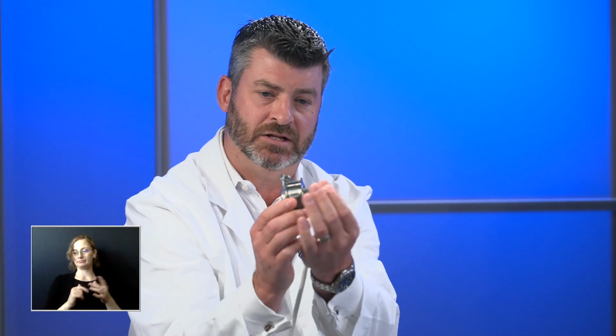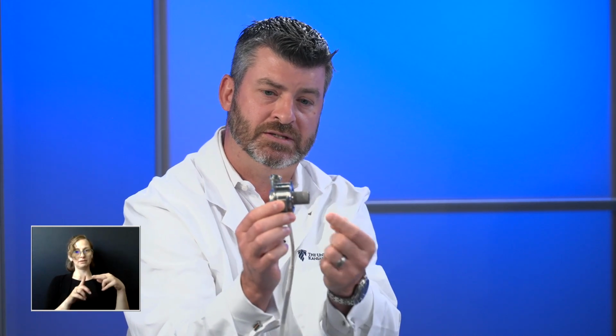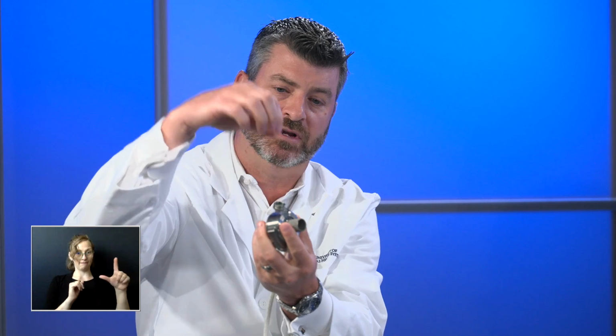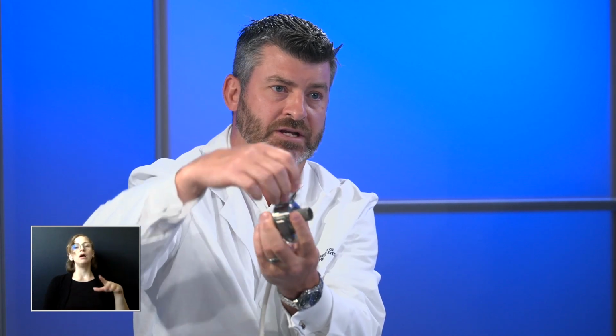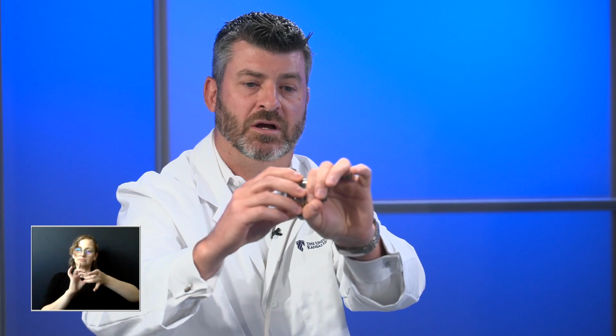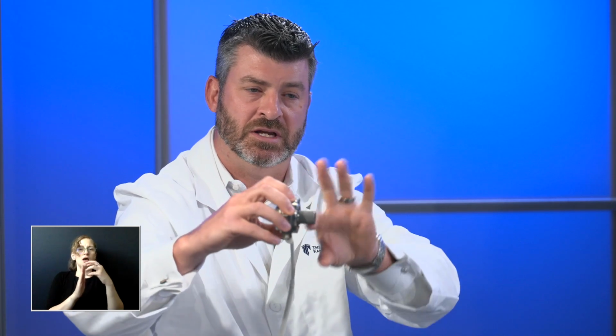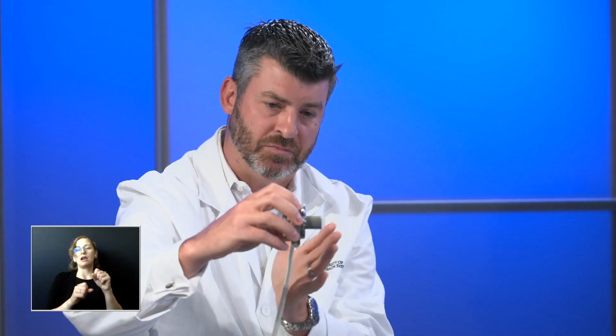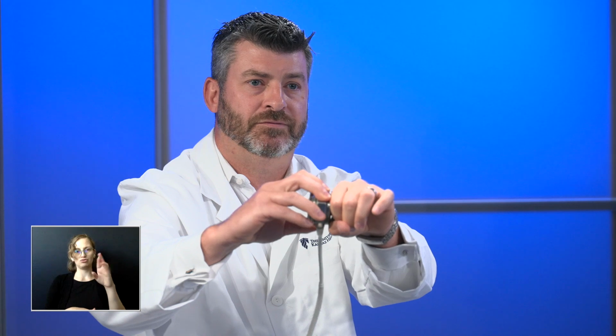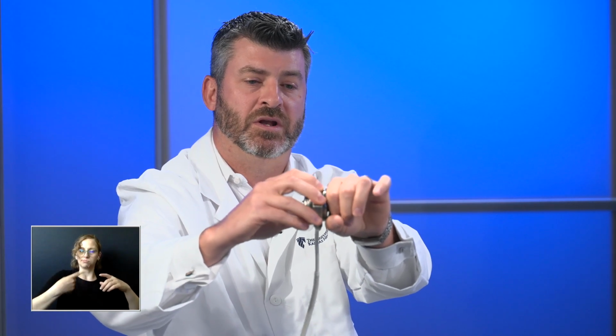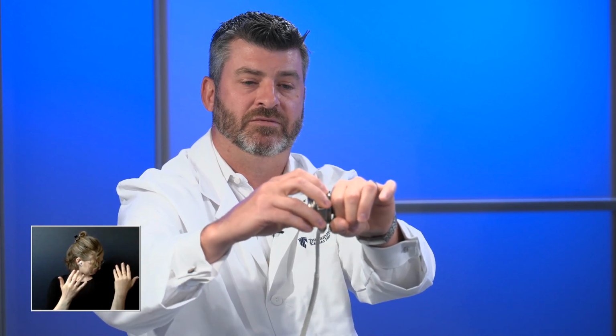this pump sticks into the left ventricle, and what this problem with sealing is, it's hard to show, but there's a very sophisticated clip device that attaches to the sewing cuff, and then you click this in. And what people had been experiencing is, if this is off a little bit or malpositioned a little bit, you get air entrainment into the ventricle, because it's spinning, and by, what's it called, the effect.